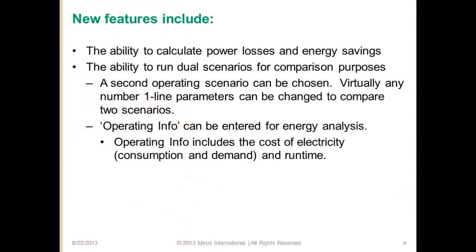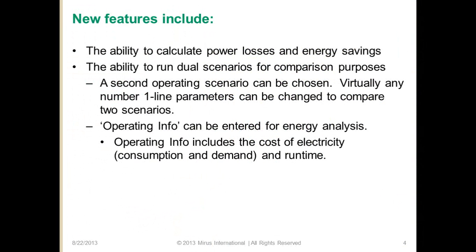New features include the ability to calculate power losses and energy efficiency, also the ability to run dual scenarios. A second operating scenario can be chosen where virtually any number of one-line parameters can be changed to compare. For example, VFDs with AC line reactors can be compared with VFDs with the Lineator AUHF. Operating info that includes the cost of electricity and runtime can be entered for energy analysis.